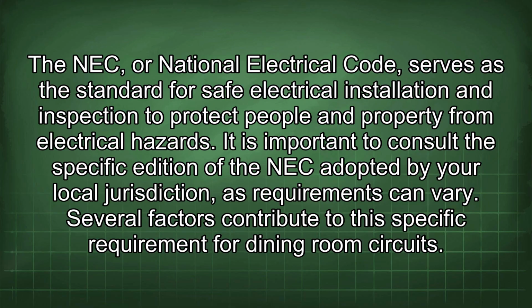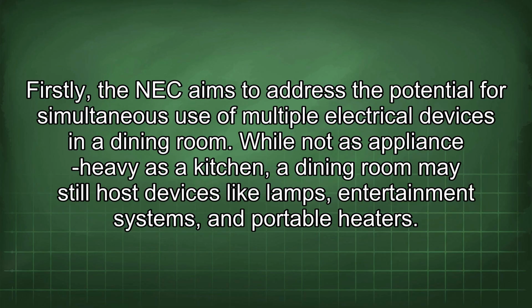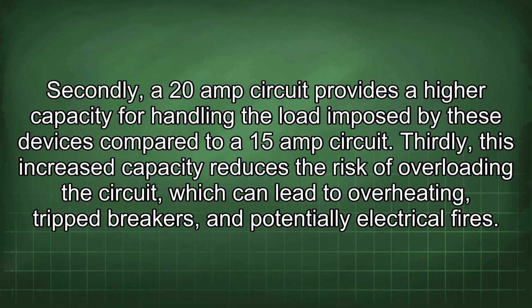as requirements can vary. Several factors contribute to this specific requirement for dining room circuits. Firstly, the NEC aims to address the potential for simultaneous use of multiple electrical devices in a dining room. While not as appliance-heavy as a kitchen, a dining room may still host devices like lamps, entertainment systems, and portable heaters. Secondly, a 20 amp circuit provides a higher capacity for handling the load imposed by these devices compared to a 15 amp circuit. Thirdly, this increased capacity reduces the risk of overloading the circuit, which can lead to overheating, tripped breakers, and potentially electrical fires.